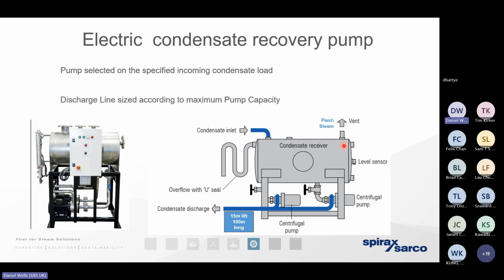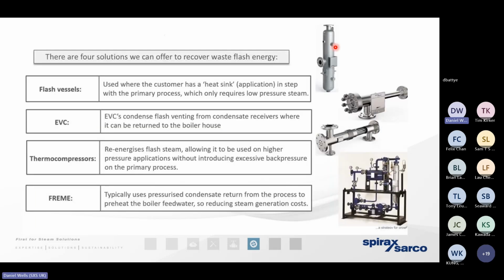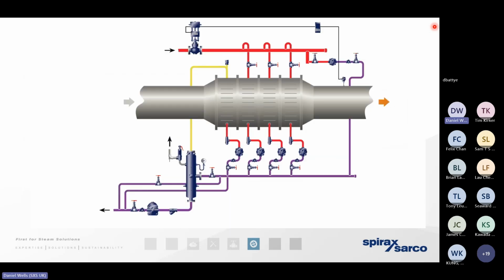But of course, the only way we can allow that condensate to cool down is by allowing the pressure drop, and the steam that is going to be produced to expand and to be vented away very, very quickly. So we need to allow that expansion to take place. Of course we do, but there's no reason why we can't recover the heat energy from it. The question we want to ask ourselves is, first of all, the mass of condensate that we're talking about and the extent to which that condensate is depressurizing, because that is going to tell us the mass, the volume, and the energy content of the steam.